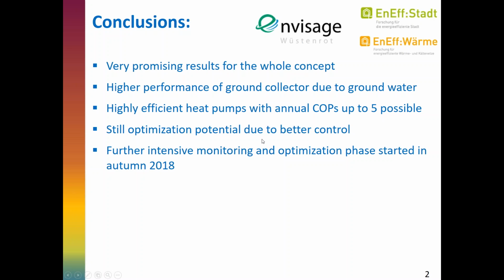We are still optimizing these heat pumps. What we found is that different heat pumps show very different control behavior, some switching on and off permanently, some operating more constantly. This also leads to a difference in the COP and the performance of the systems.